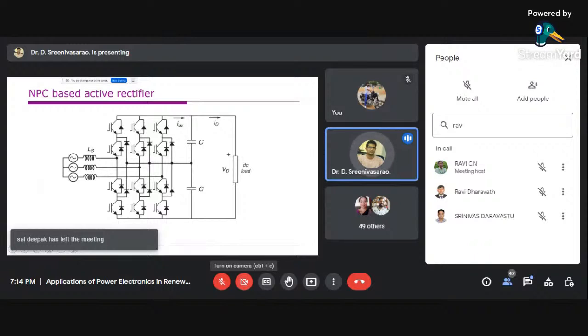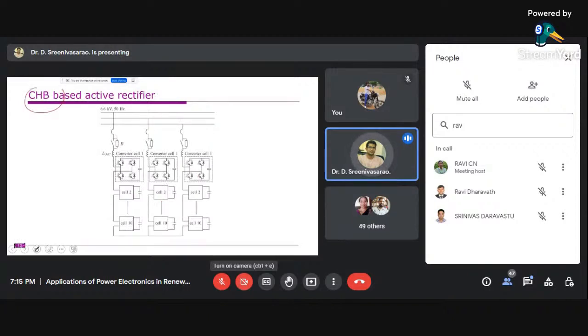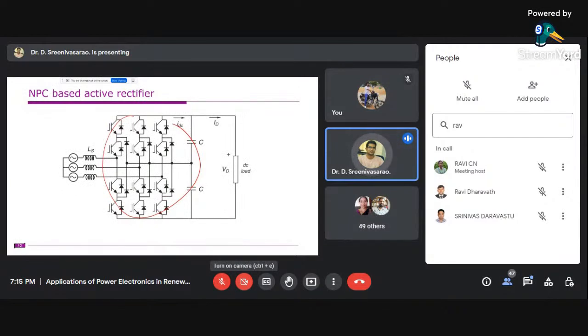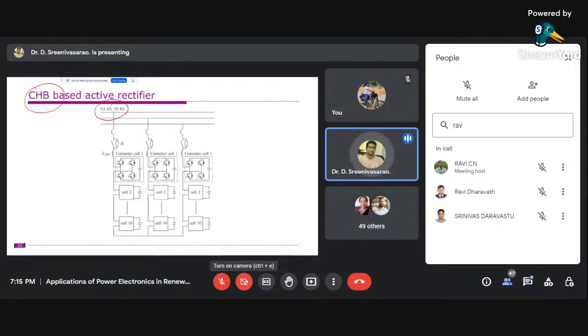If you want to go for high power applications, we have multi-level inverters, known as active neutral point clamped or the diode clamped multi-level inverter, which is used as an active rectifier. Another one is the cascaded H-bridge inverter, also used as an active rectifier for high voltage applications - the voltage is around 6.6 kV. Depending on the power levels, we have different options: low voltage options, slightly higher voltage, medium voltage, and high voltage applications.